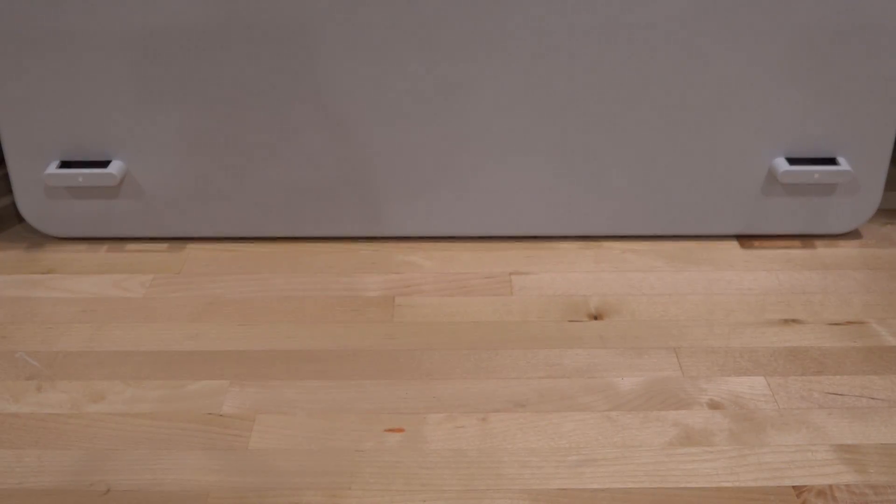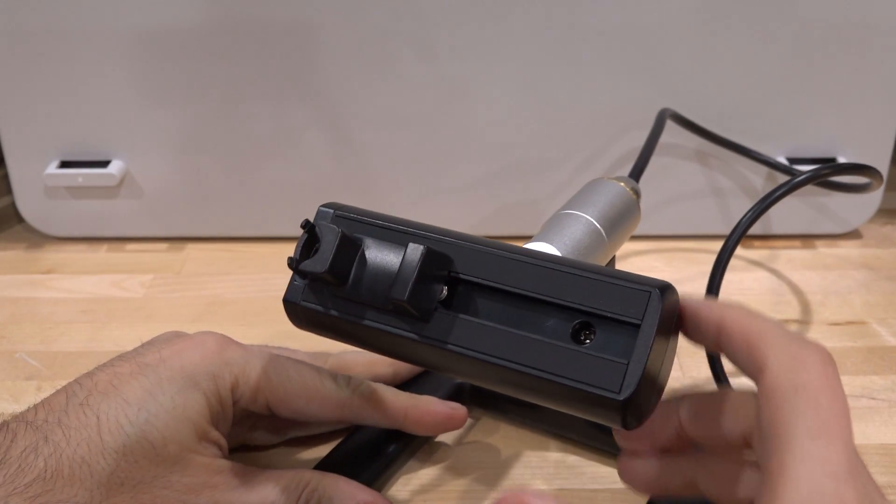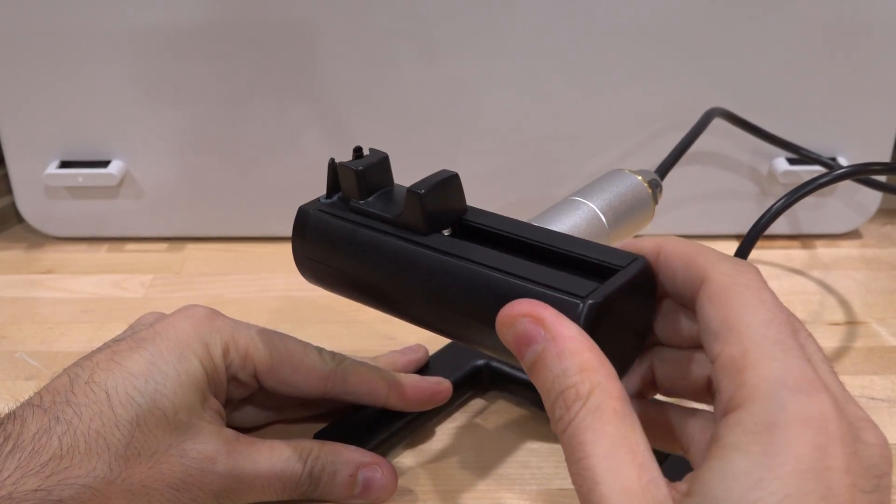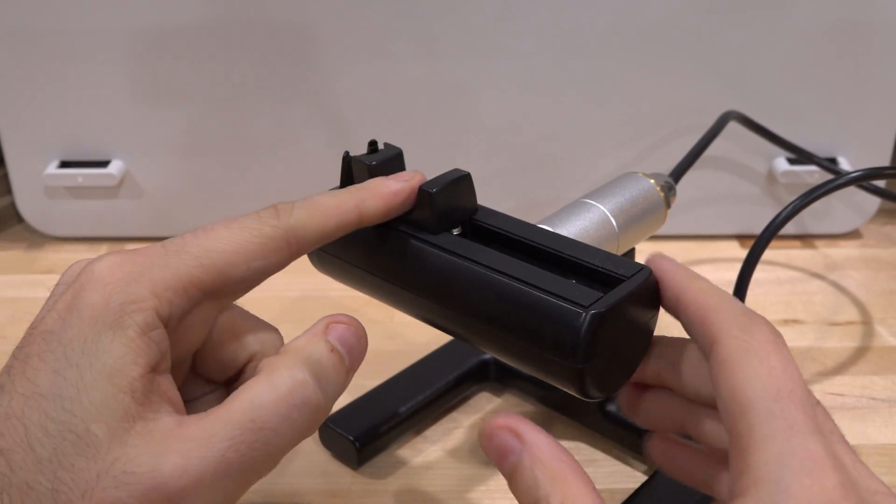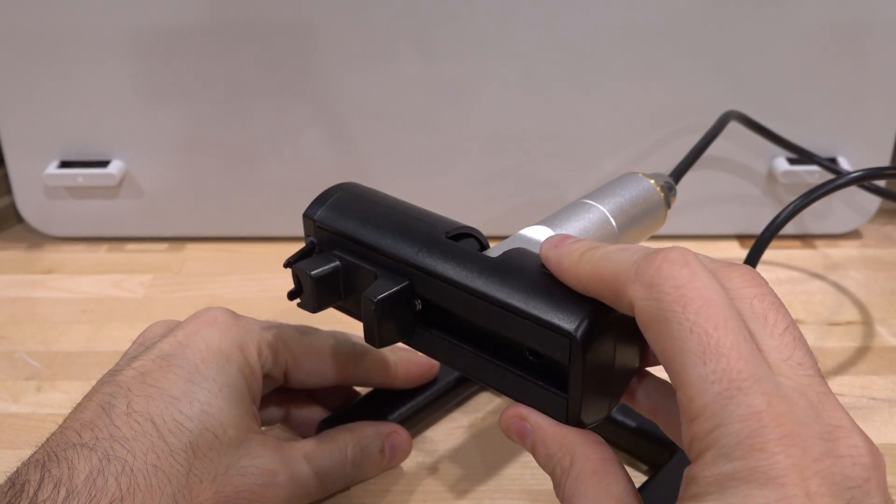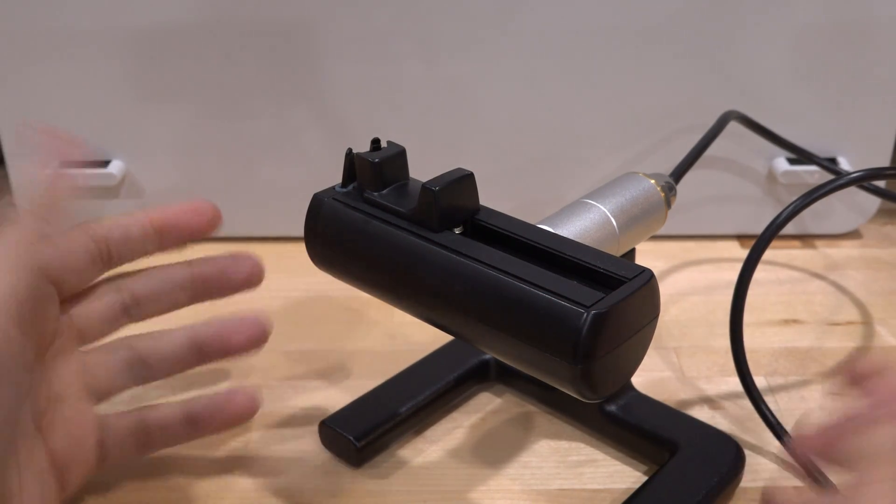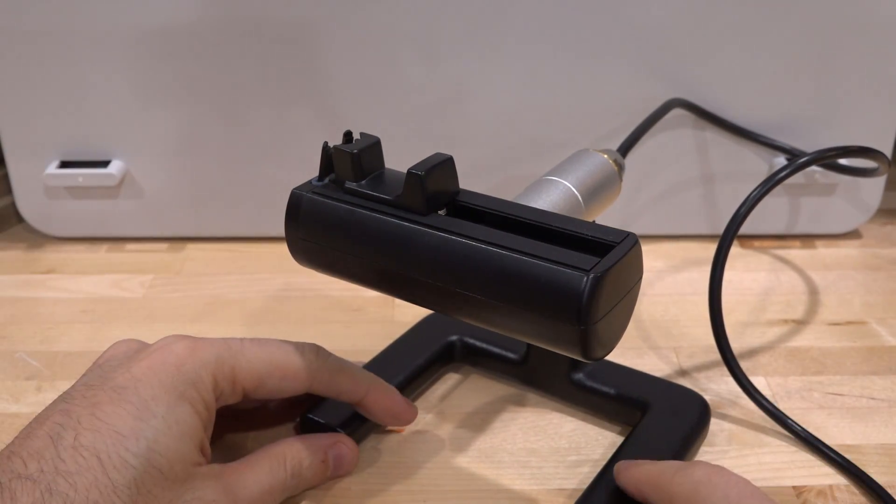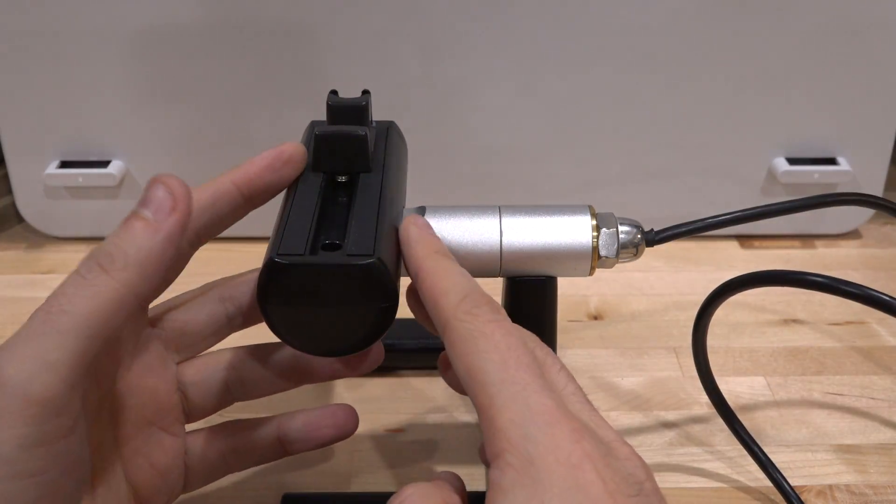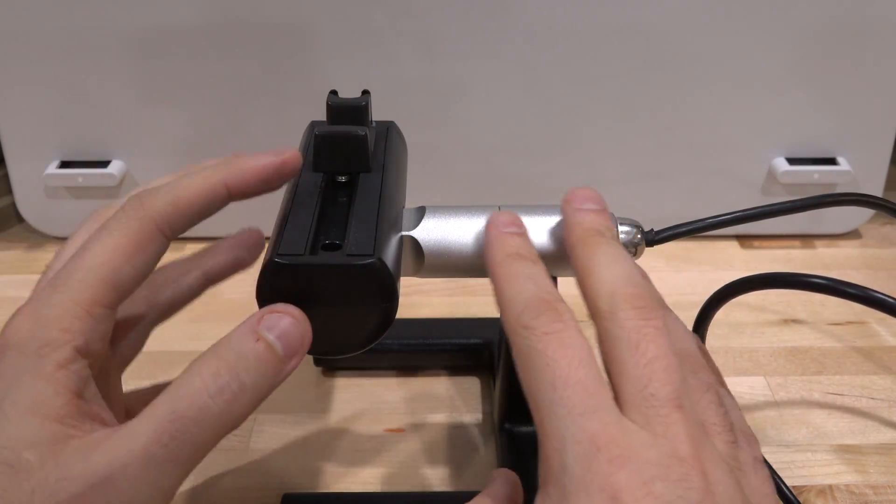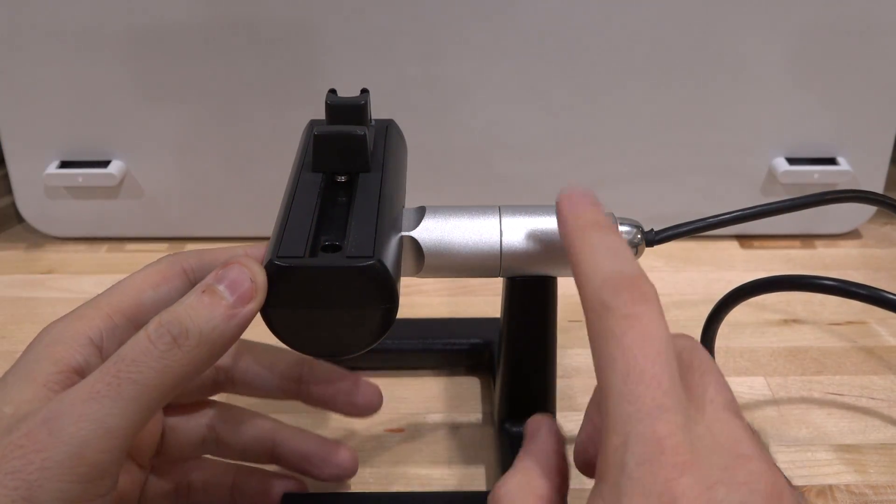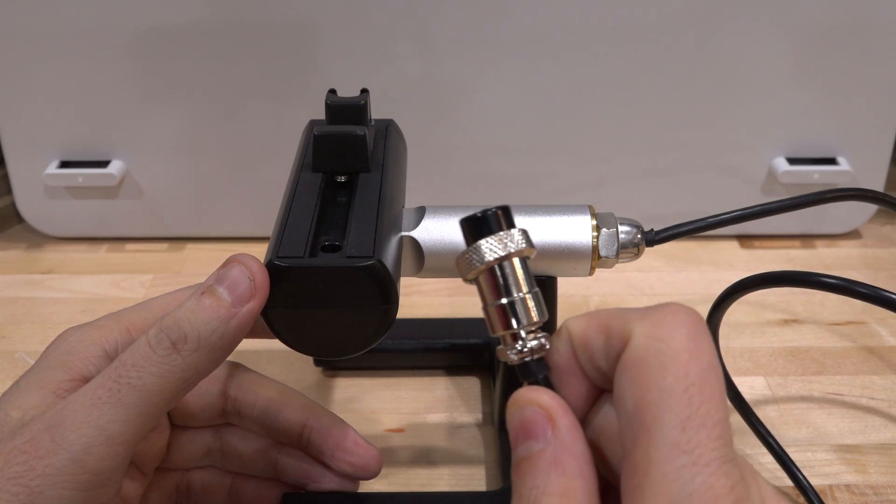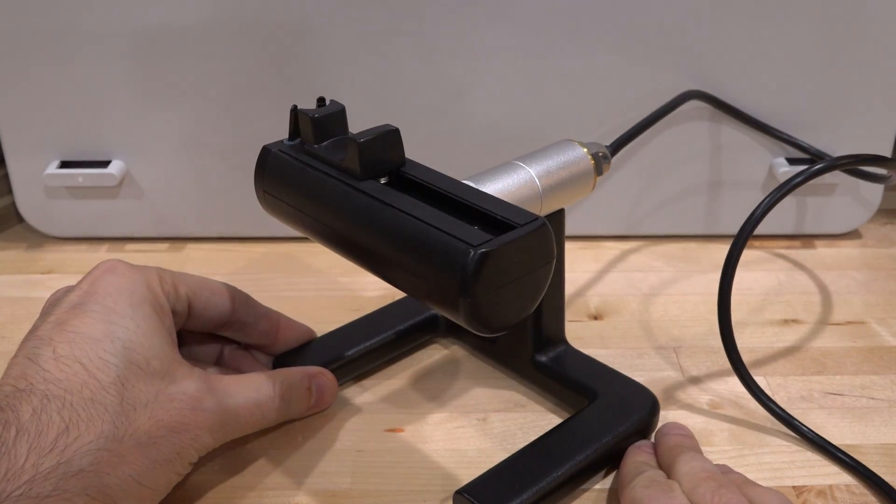The microphone that it comes with is an interesting apparatus itself because it allows you to basically rotate it in a few degrees of freedom. I think it also goes this way. The reason you would want to do that is because when you put the watch in here you want to see if the gravity or the orientation of the watch has any effect on how it runs. You can imagine for a mechanical component that will have an effect. I don't see any place for a hole for the sound to go through, so I think this is all mechanically coupled. It's essentially using the conduction of sound through this to measure it and pick it up from there and essentially connect to the instrument.